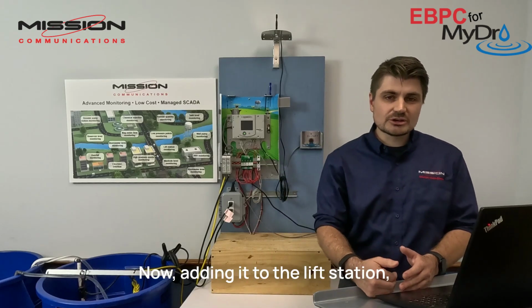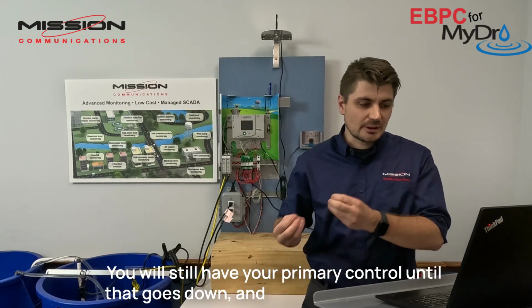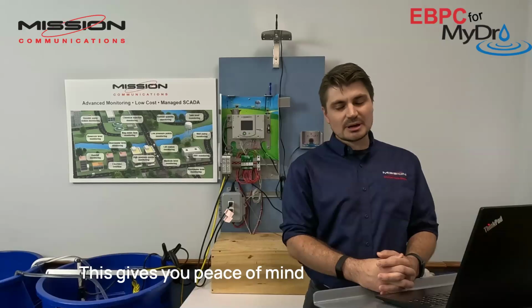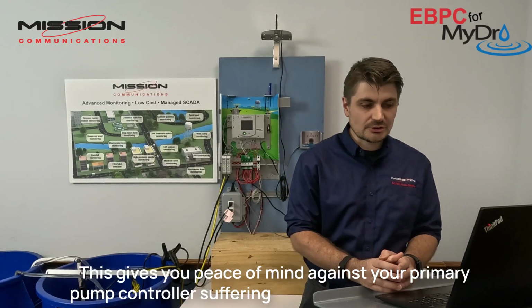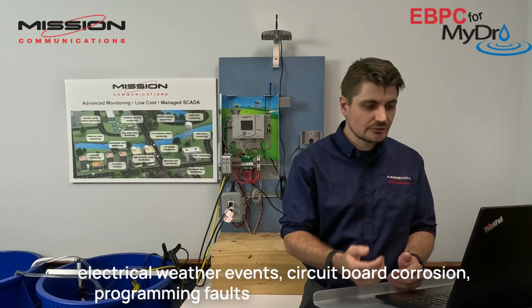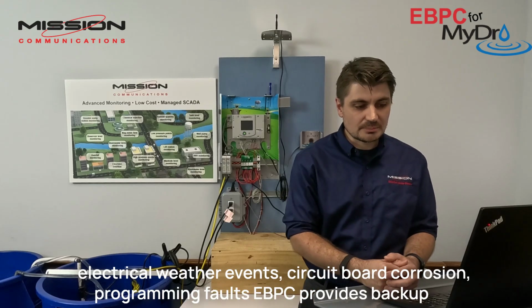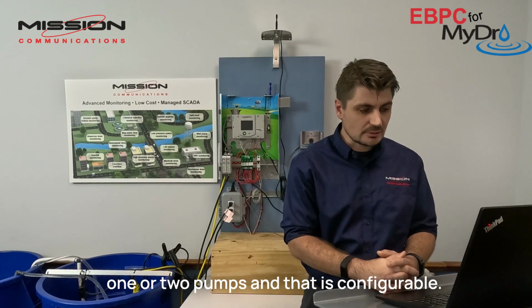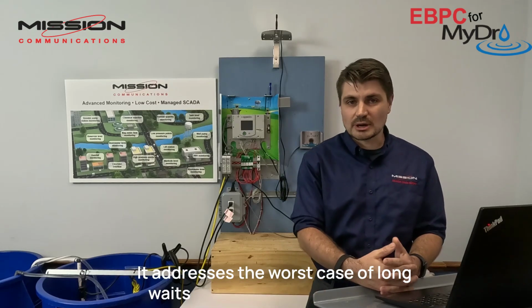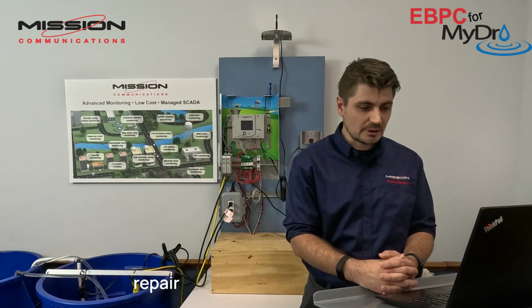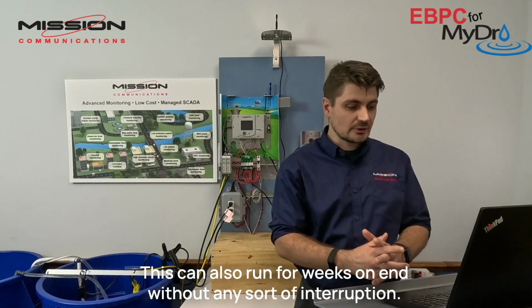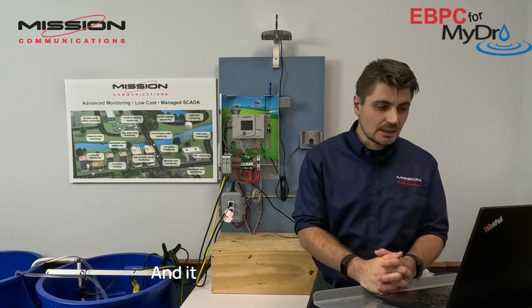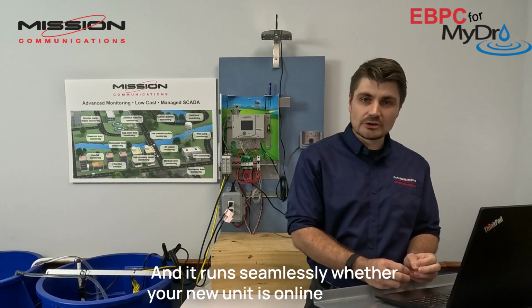Now, adding it to the lift station, of course, is for emergency use only. You will still have your primary control until that goes down, and that's where we kick in. This gives you peace of mind against your primary pump controller suffering any sort of damage due to electrical weather events, circuit board corrosion, programming faults. EBPC provides backup for 1 or 2 pumps, and that is configurable. It addresses the worst case of long waits for your parts coming in to repair your primary pump controller. This can also run for weeks on end without any sort of interruption, and it runs seamlessly whether your unit is online or offline.